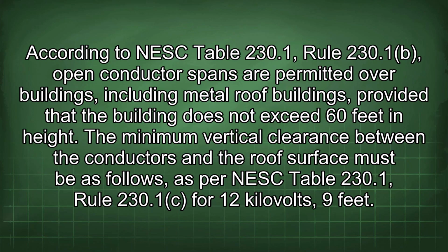According to NESC Table 230.1, Rule 230.1, b. Open conductor spans are permitted over buildings, including metal roof buildings, provided that the building does not exceed 60 feet in height. The minimum vertical clearance between the conductors and the roof surface must be as follows, as per NESC Table 230.1, Rule 230.1 C: for 12 kilovolts, 9 feet.